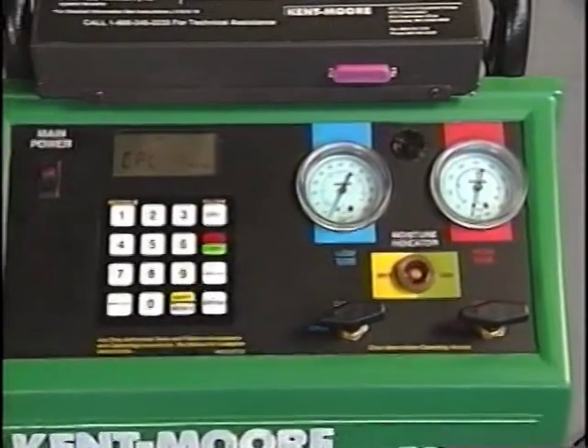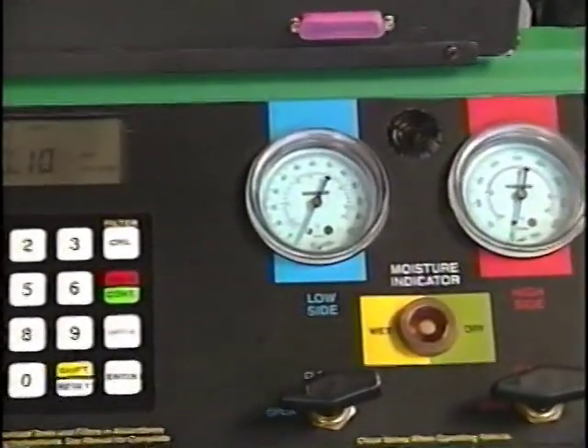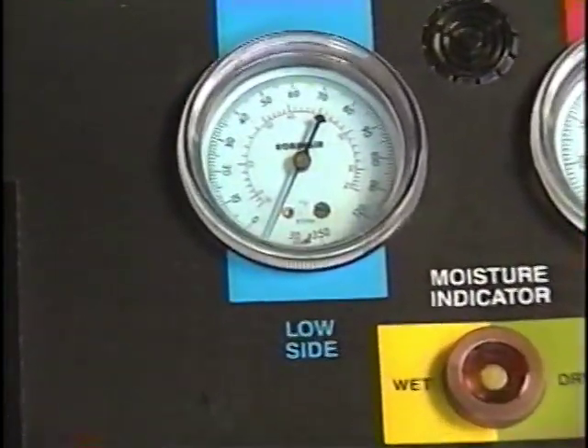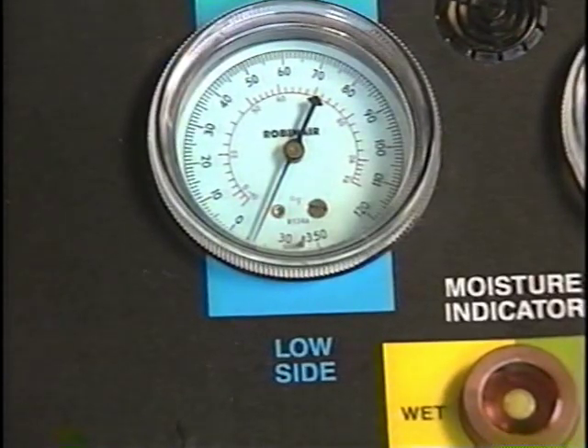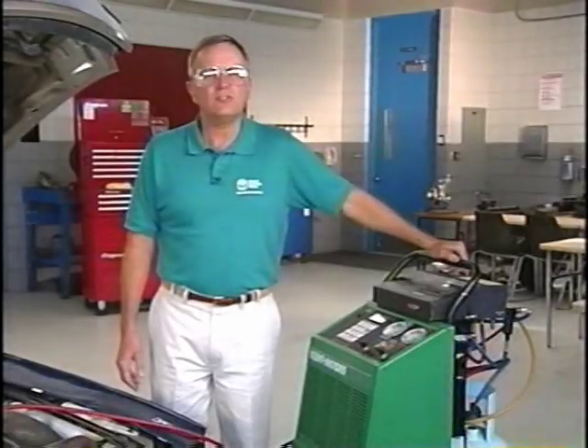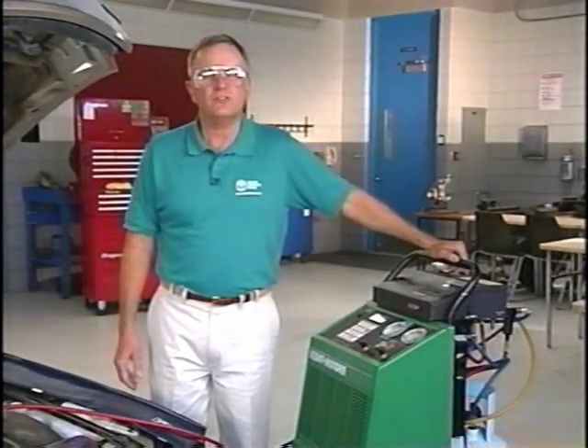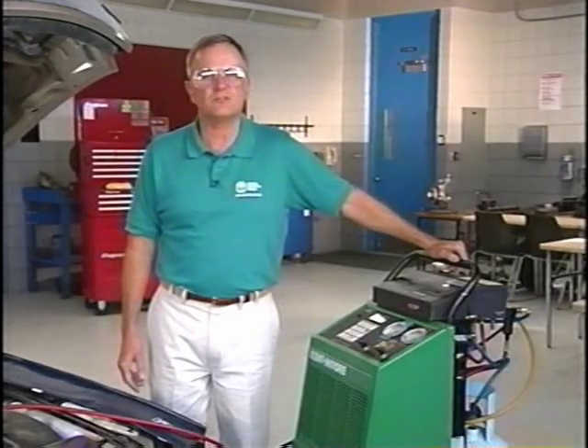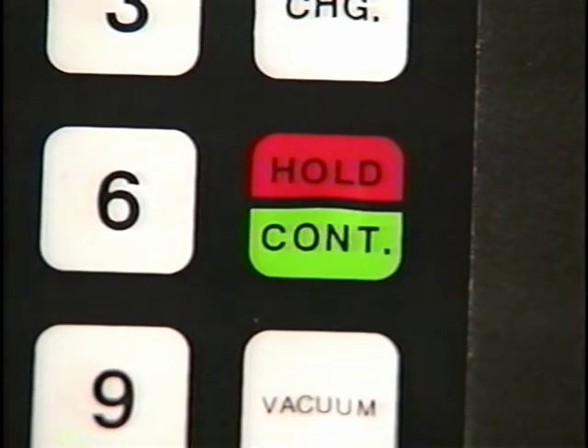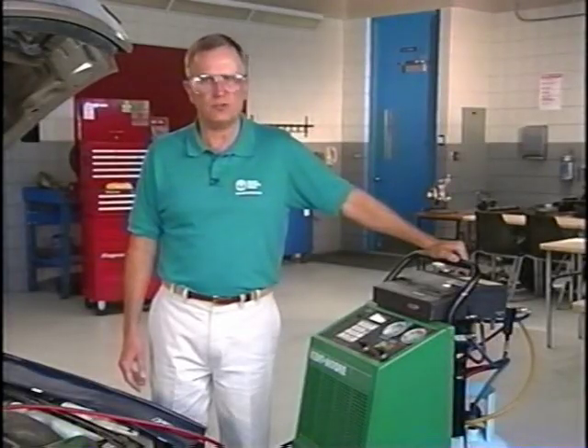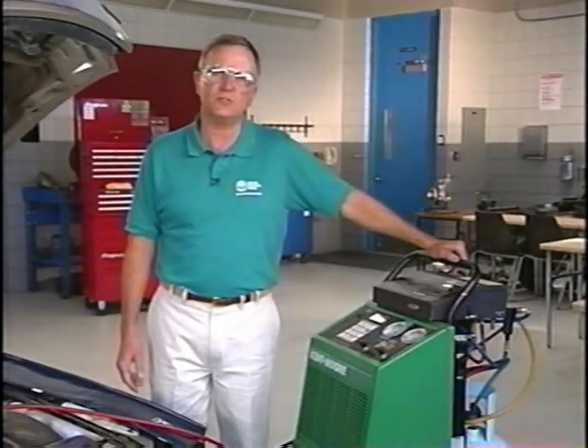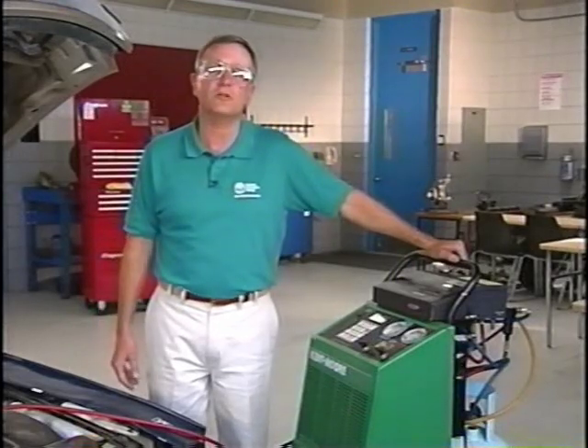Now we'd like to take a look at the low side gauge to make sure we maintain a vacuum in the system. And that's an indication that the refrigerant has been fully recovered from the system. If there's a rise in the pressure on the low pressure gauge, that's an indication that there's still refrigerant left in the system. Push the Hold Continue button to continue the recovery process. This may take a couple times in order to achieve and maintain a proper vacuum in the system, indicating the system has been fully recovered.